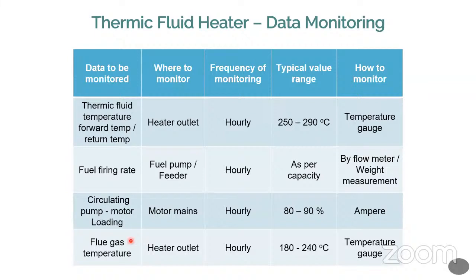Monitoring the flue gas itself will tell you whether the boiler or TFH is operating properly or not. Experienced boiler operators or boiler supervisors regularly check the chimney outlet and the color of the flue gas. Based on the color, they tell how to adjust the flow rate of the water, how to adjust the feed rate of the fuel, and how to adjust the ID fan air by operating the speed of the ID fan, either by the throttling method or by increasing the speed with the help of a VFD control method. Those things are taken care of by the supervisor, and an experienced supervisor will know how to operate based on the color of the flue gas.